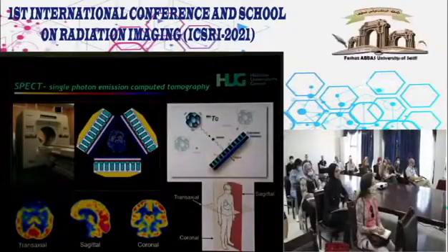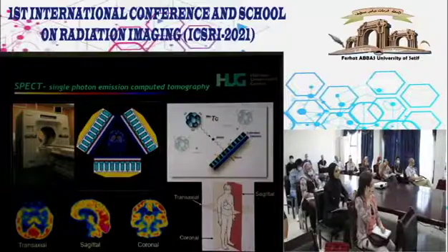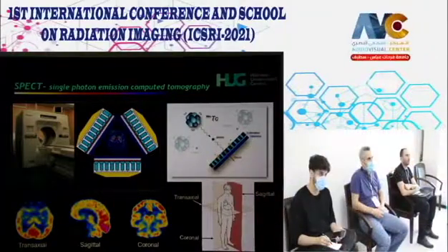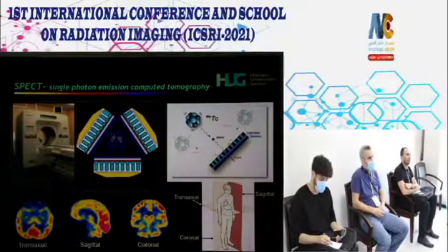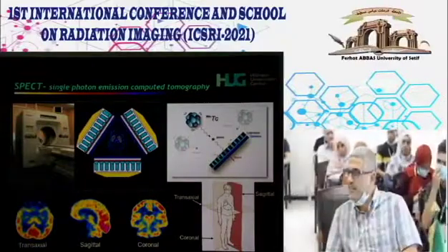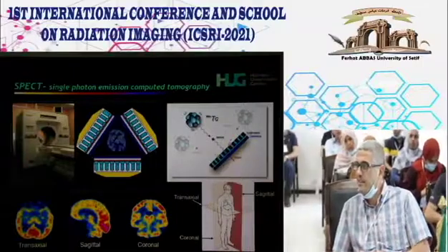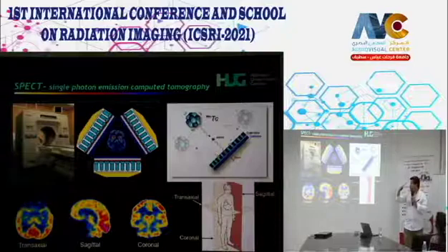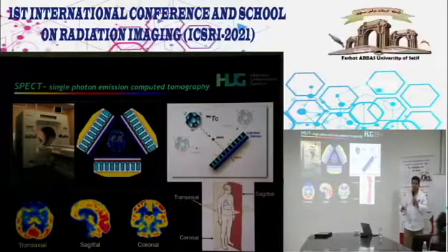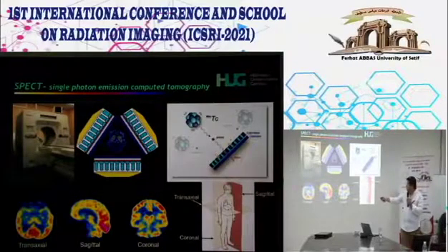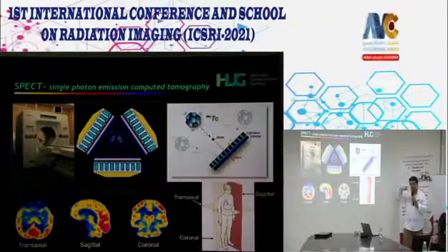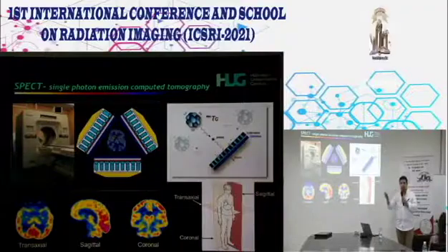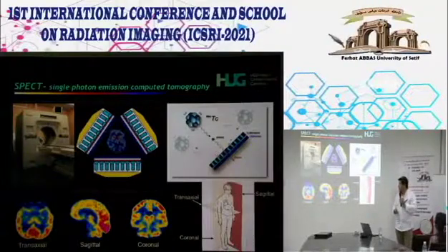So what I have said so far is for gamma cameras operating in planar imaging mode, which means generating two-dimensional projection images. And then we can use the same mechanism that I described earlier for X-ray computed tomography, which means rotating the detectors around the patient to acquire the data in multiple views and multiple angles. So this is one camera dedicated for brain imaging. We rotate the cameras around the patient to acquire multiple views, between 32, 64, up to 128 views.